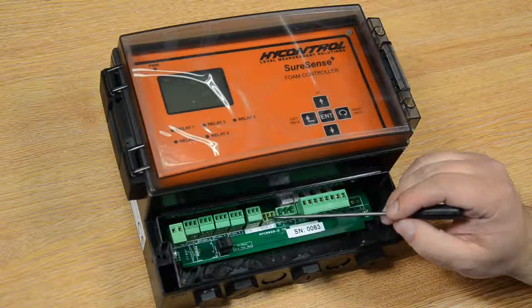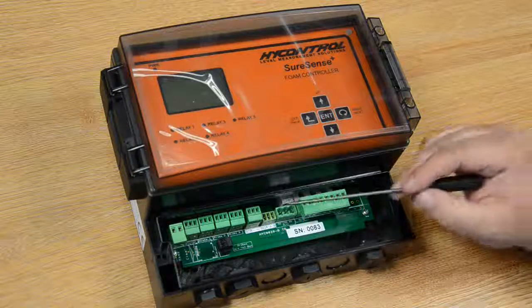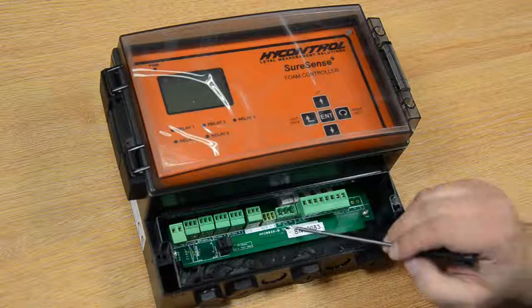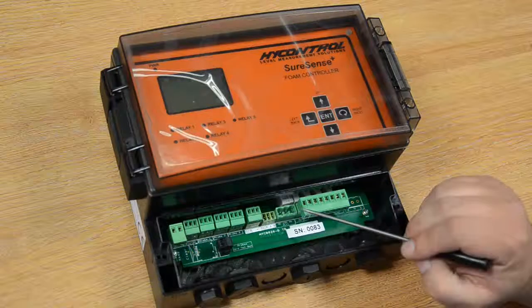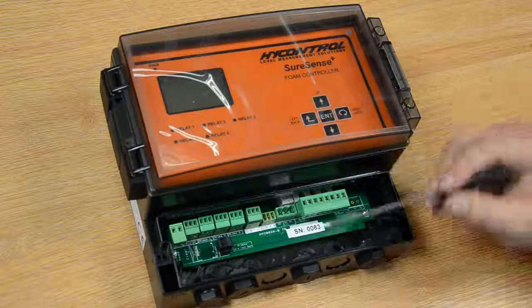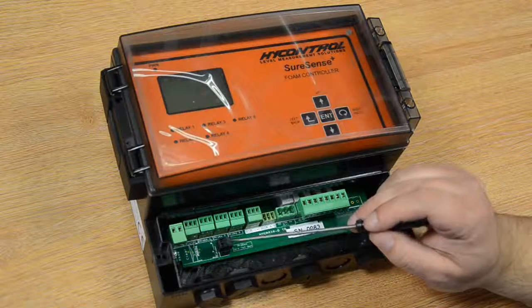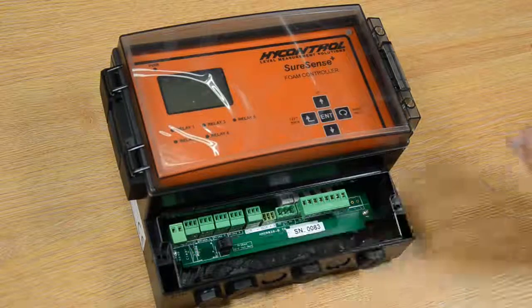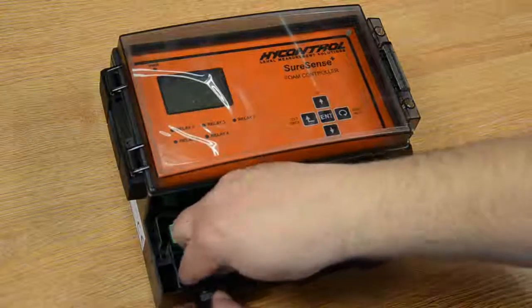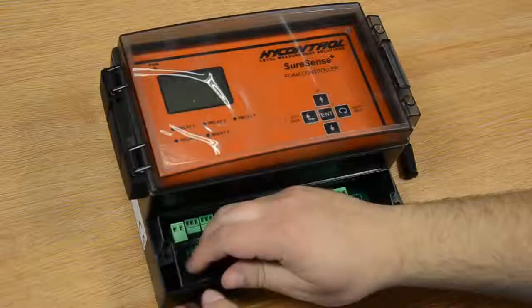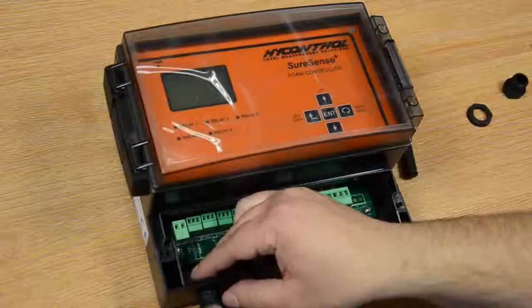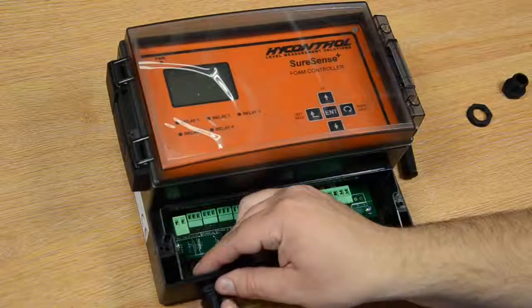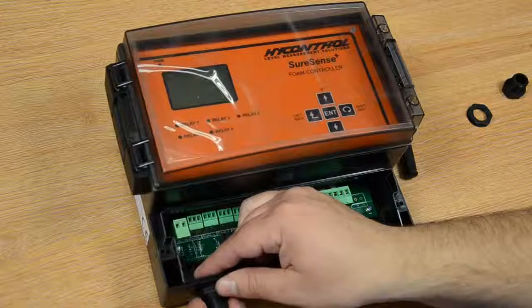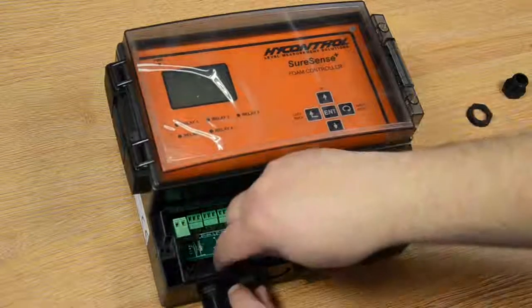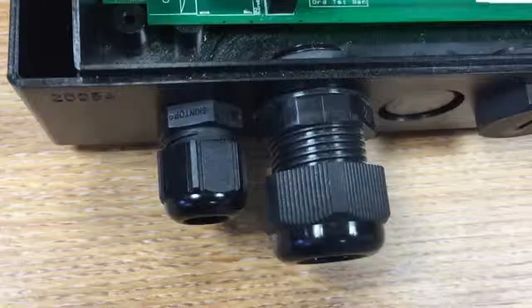We have a Modbus connection, but this is only for factory use, and then we have our relays. You'll notice relay 1 has 3 terminals and the rest have 2. This is the only relay with a common. We also have our earth returns at TB11. The first thing you're going to want to do is remove the blockers. This is so you can add the cable glands into these holes. For the power you'll need an M16 cable gland, and then your probe is a bit bigger, it's an M20.